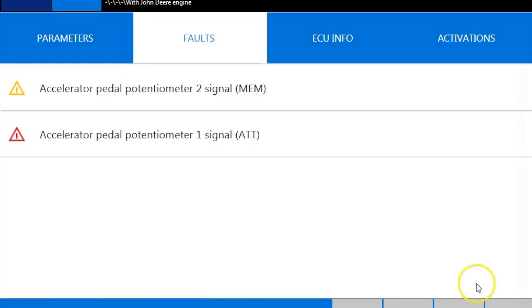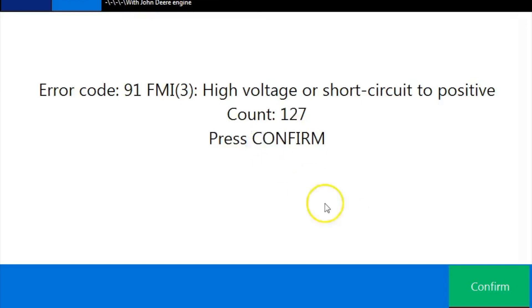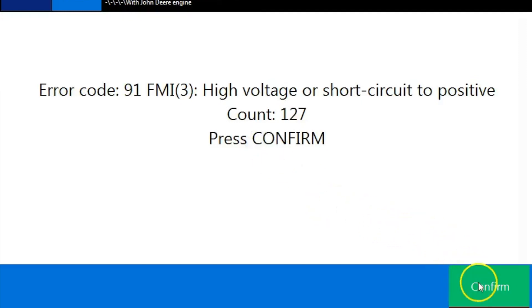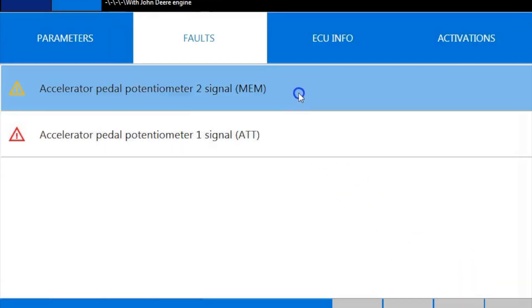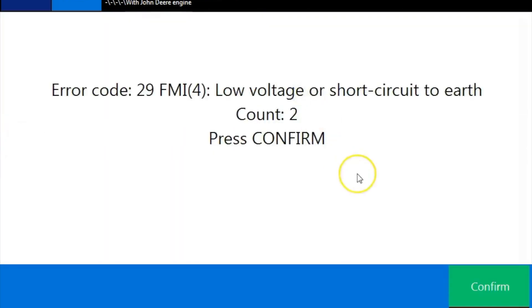Here you see you have a yellow one and a red one. That yellow one is a memorized code — it's an older code — and your red one is the active one. So we'll go ahead and pull that up first. Here you have your FMI number and your count number. Click confirm. We'll go check out that older memorized code. You can see that FMI number and count number is there also. Go ahead and confirm.